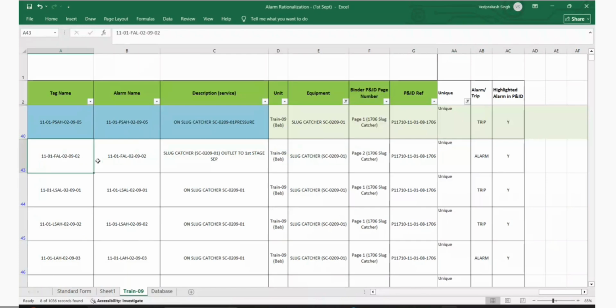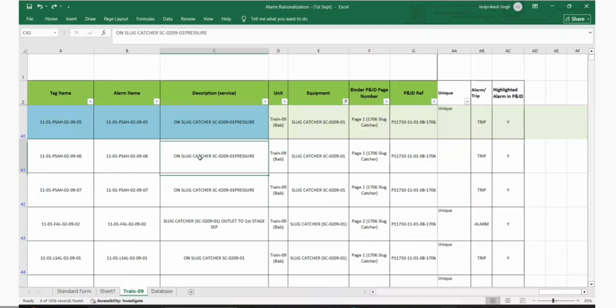Now we are going for the next alarm. So what is the next alarm? Chairman, we didn't get the answer from your end. There is a 2 out of 3 voting of transmitters, which is closing the 2 HIPS. This is the loop. This loop has multiple alarms other than these, for example deviation alarms. HIPS is generating more alarms, for example PST there are some alarms. So how will you capture those alarms?